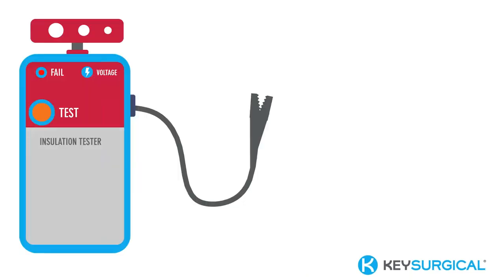So we mentioned the insulation tester a couple times throughout this presentation, but how exactly does it work? Visual inspection is a critical training component for every single sterile processing professional, but as we noted a few times already, there's more to the insulation on an electrosurgical instrument, which is where these insulation testers come in handy. It can detect issues with the insulation before it is used in the OR or on that patient. So it's important for techs to receive training on the function of the insulation tester, how to use it, and what to look for.